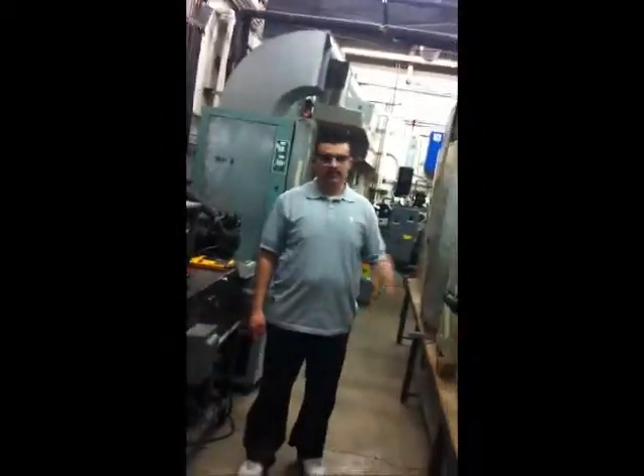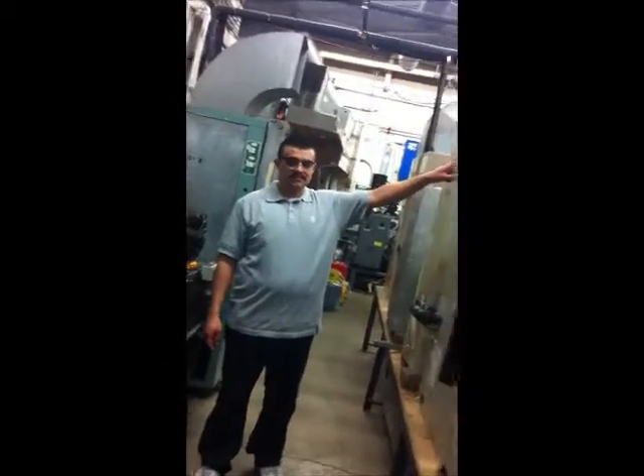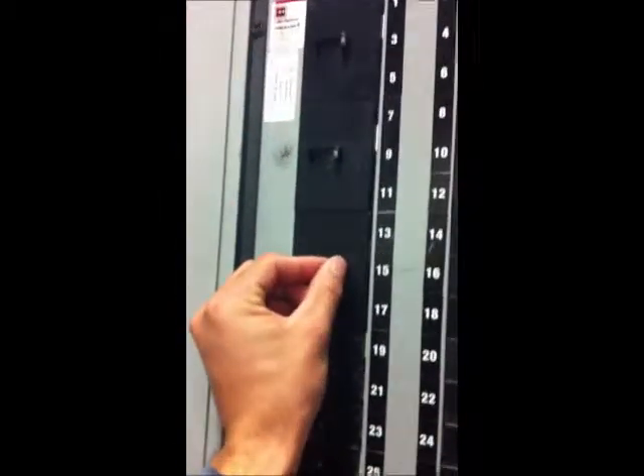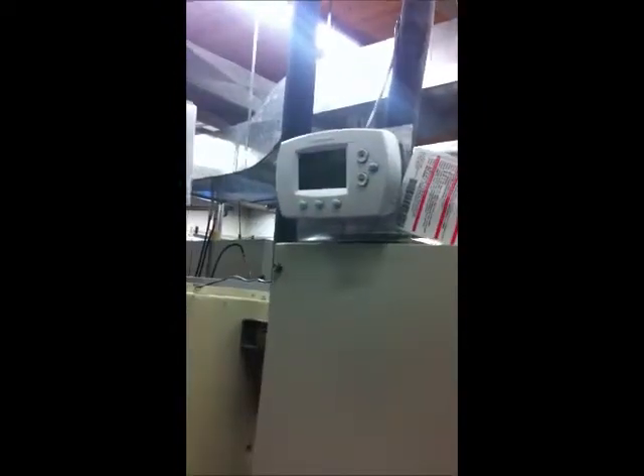The first step to troubleshoot the electric furnace is that Jaime over here is going to turn on the circuit breaker. And Edgar over there is going to turn it on and see if it's working or not. Okay, so we're going to make sure it's on. And in this case, it's 15. And we're going to crank up the thermostat, see if it's going to turn on or not.